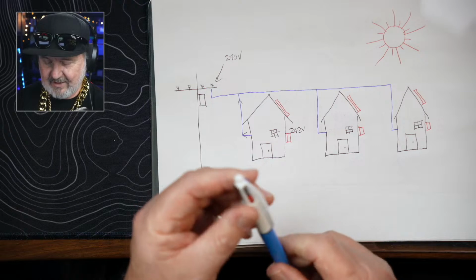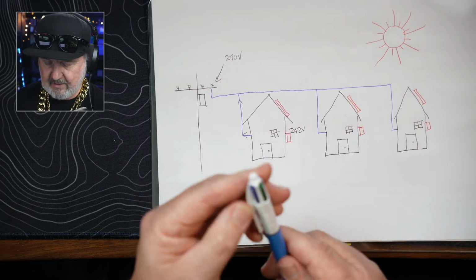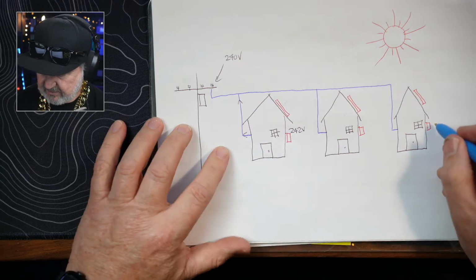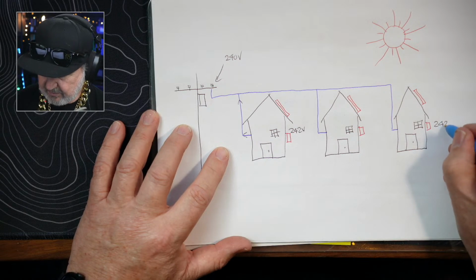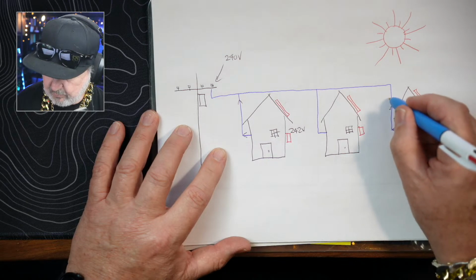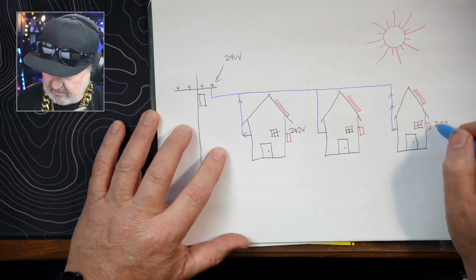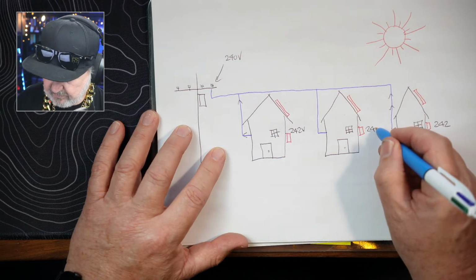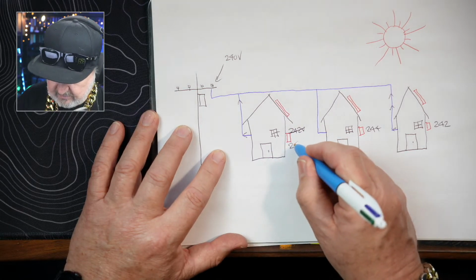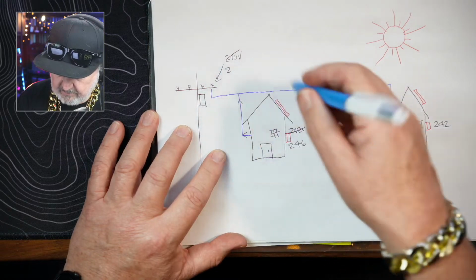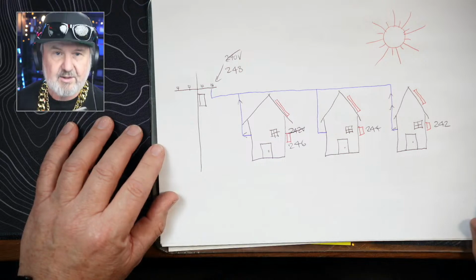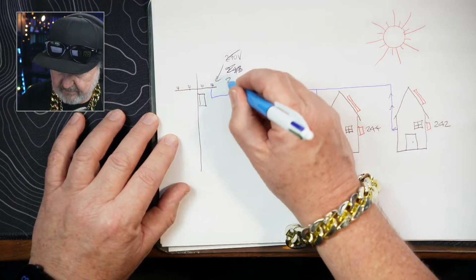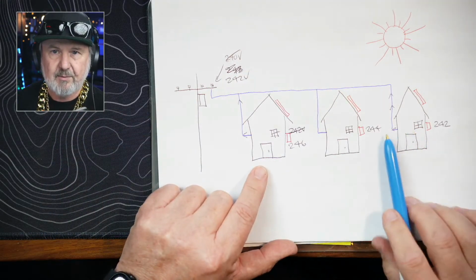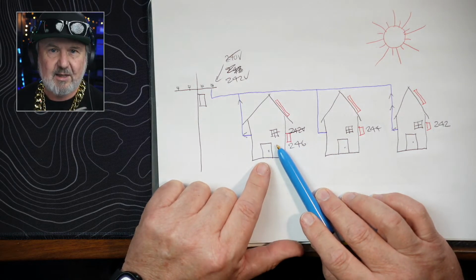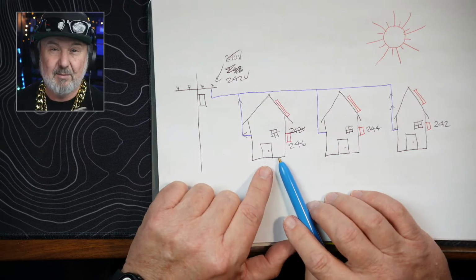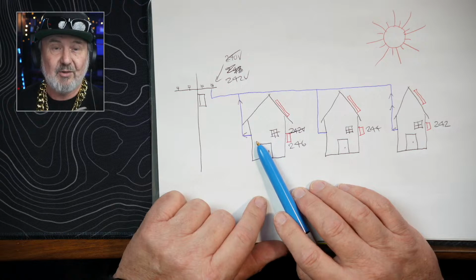Now what we're going to see happen is a cascading voltage increase. So this house might be at 242, so it's pushing up this wire. At this point it's raised a little bit. This house will have to raise it even more, 244. This house even more, 246. And now it's gone up to 248. So this one here will be slightly lower, 242. It's a cumulative problem. The more generators there are on the same feeder, this is a single phase here, the more that voltage rise will occur and push up everyone's voltage in the street.